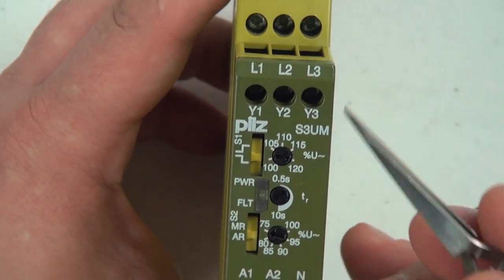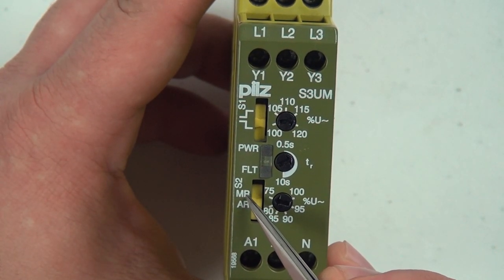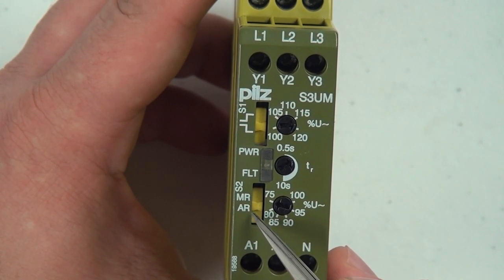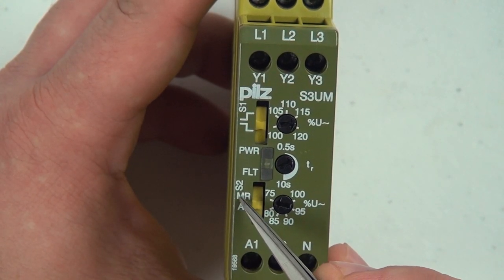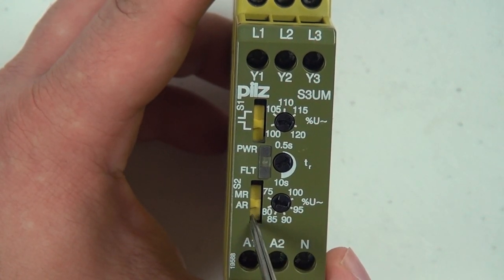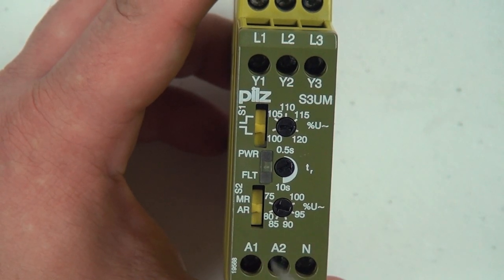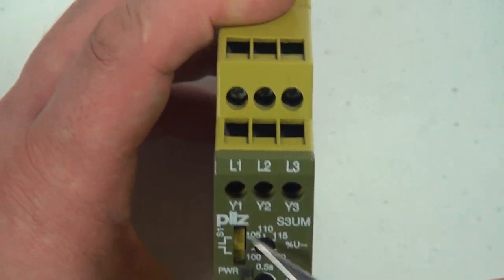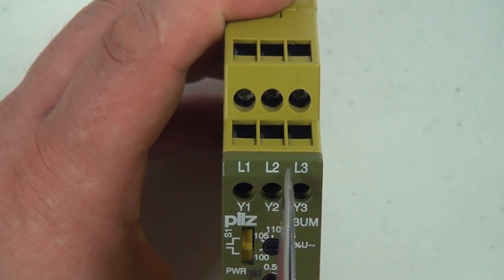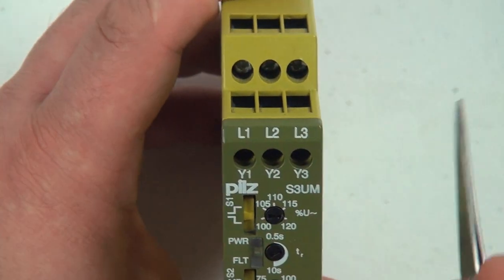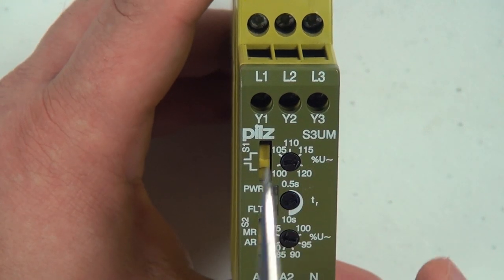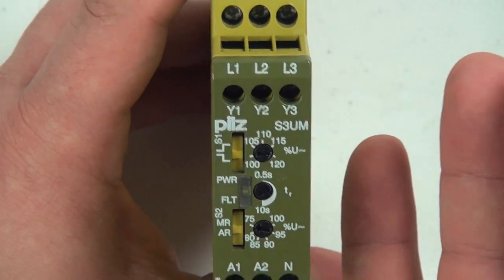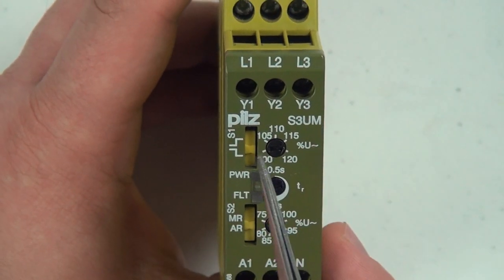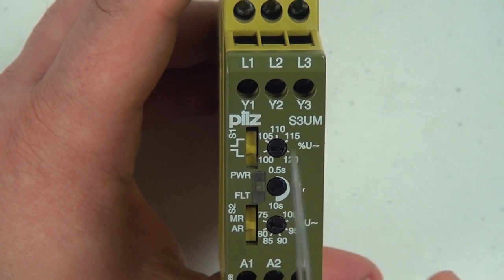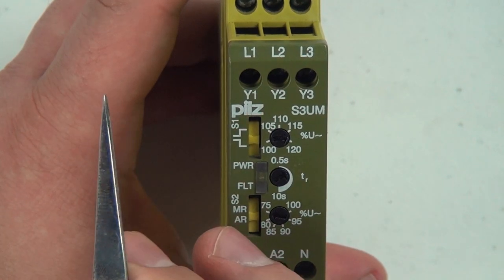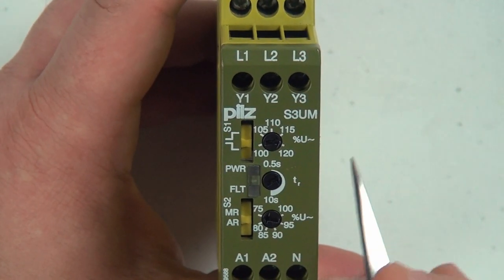What does that mean? As you can see down here, you have MRAR, and MRAR stands for manual reset and automatic reset. Currently, this relay is an automatic reset, meaning that whenever the power quality on L1, L2, L3 is good, the relay will automatically switch on or off. It depends on how this is set, whether it's normally open, normally closed, but the relay will automatically transition from one state to the other state.